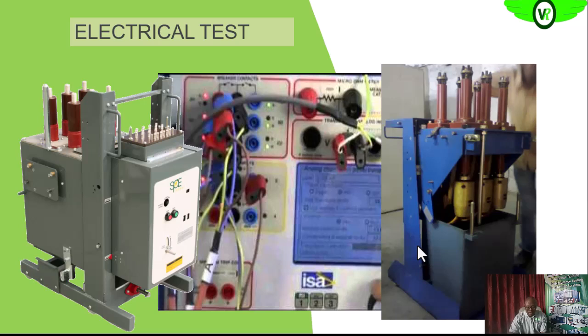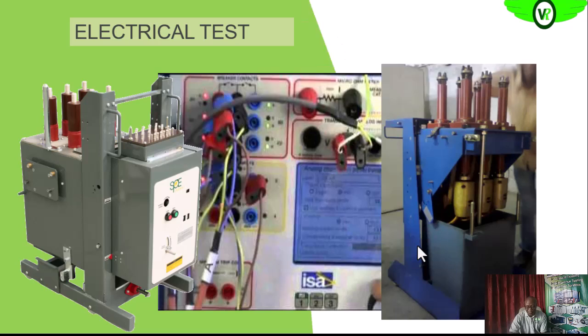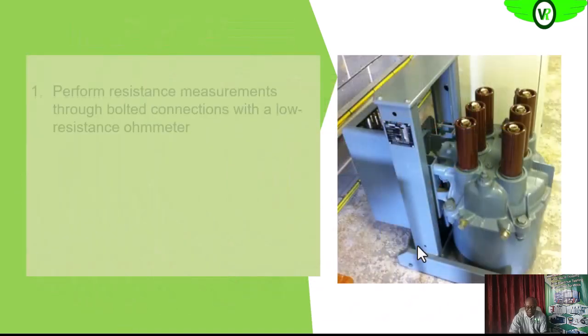We'll be doing that resistance test on bolted connections. We'll also be doing the resistance test on the contact to see that there are no unnecessary resistance developing on the contact. We'll also carry out the insulation resistance tests between the phases and between phase and ground, and some other tests on the circuit breaker that we'll see as we go along.